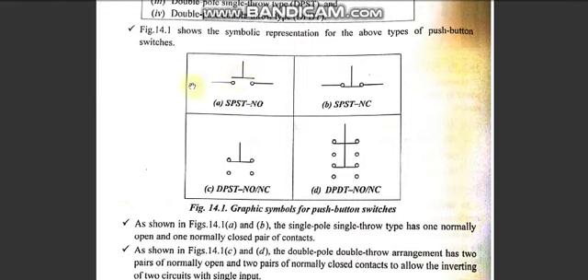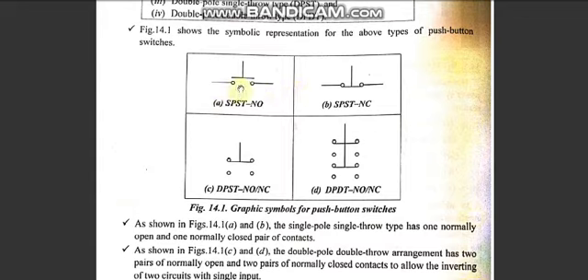Normally open means the contact is broken by default — when you push the button, the electrical current passes through; when not pushed, the circuit remains open. Normally closed means the circuit is closed by default and current always flows — when you push the button, the current is cut off.